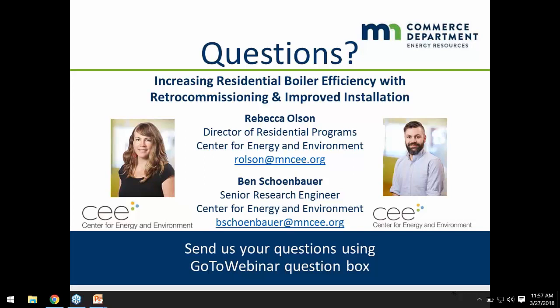I've heard that regular maintenance and cleaning of the water side of the domestic hot water heat exchanger is important to prevent the buildup of calcium and other hard water minerals that could affect the efficiency. Did you look at this at all when you were looking at the degradation of the efficiency of the boiler installations that had domestic hot water loops and had been in for 5 years? Even if you didn't look at this, do you have anything to say about that issue in this type of system?